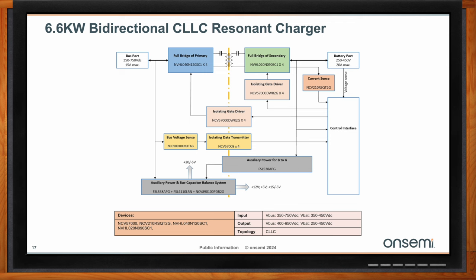Or we can interleave two totem pole PFCs. That means two high frequency half-bridge legs and two inductors will be used, so the power will be divided like 3.3 plus 3.3, 6.6 kilowatt. Then on the LLC stage, in 3 kilowatt we have the half-bridge LLC. In a 6.6 kilowatt application, we will have a full bridge circuit on the primary, that means two half bridges, and the transformer is connected between the center points of the two half bridges.